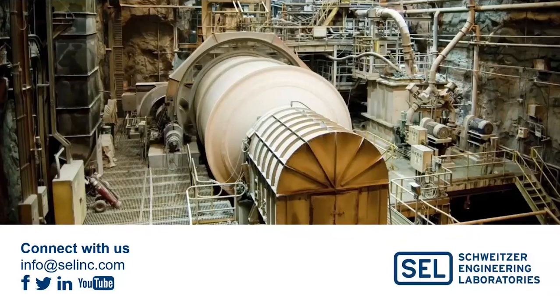I've got a question here. Can this be used with synchronous motors? In principle, yes. Even from the point of view of the transfer, it's an easier job for the relay, because when you disconnect a synchronous motor bus, the frequency remains at whatever it was before, basically nominal, and then it decays from there. Not everyone who owns synchronous motors wants to do a bus transfer on synchronous machines, and that is a customer decision, but it makes the transfer easier. You have to be sure that you have enough inertia and that your motors are robust. But that's not a problem for the relay. That's a consideration that the customer has to make. All right, yes, you can use it.